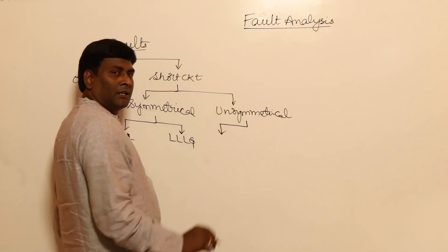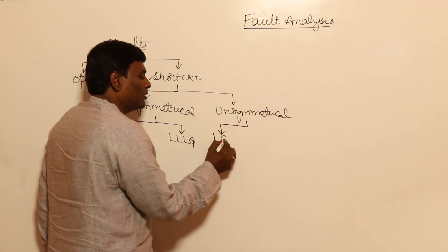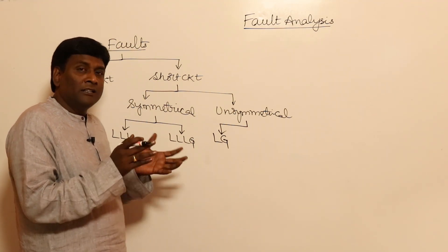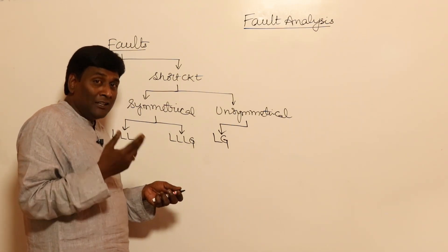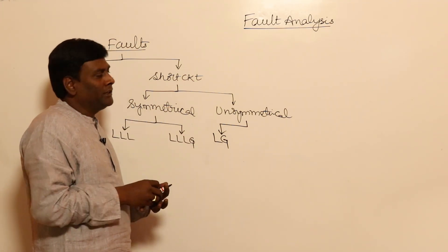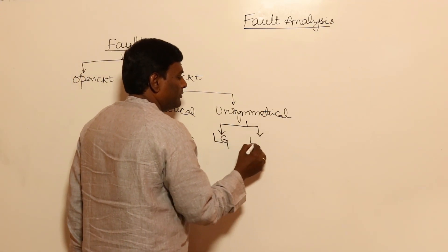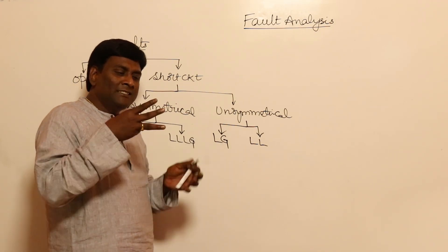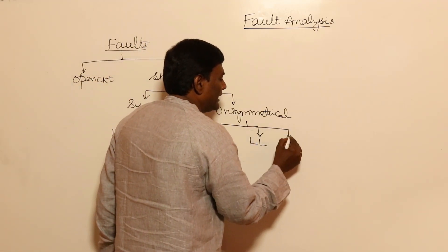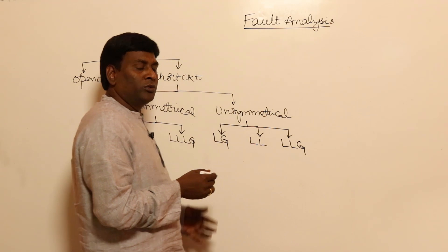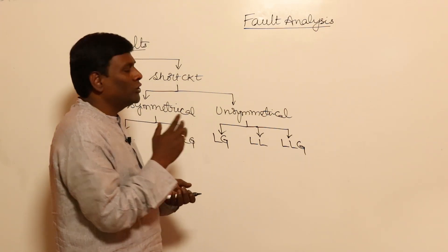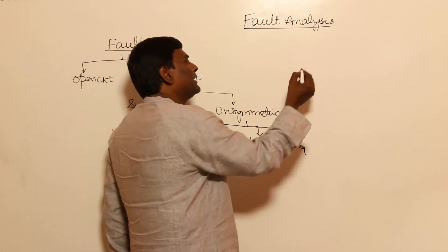In unsymmetrical faults, for example, if one line is grounded (L-G fault), the remaining two lines are healthy, so we cannot use a single-phase equivalent circuit. Another type is the L-L fault where two of the three lines are connected together while the third is intact. There is also the L-L-G fault where two lines are connected with the ground. These are the classifications of unsymmetrical faults.